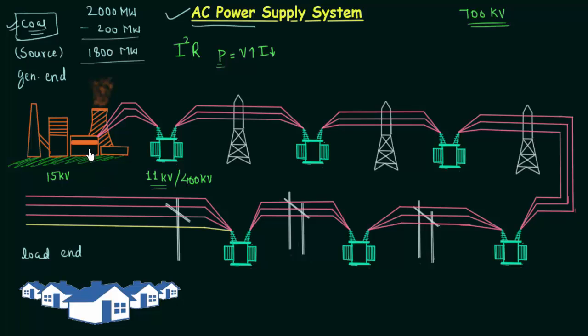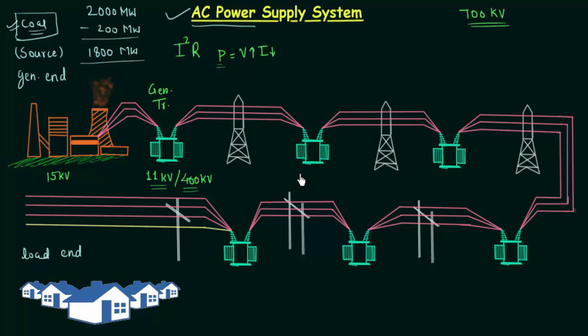Along with the generator, we require a transformer acting as a step-up transformer, which we call the generator transformer. It is the same as other power transformers, but its operation is different: the generator transformer always works as step-up, whereas general power transformers can work as step-up or step-down. So there is always a generator transformer associated with the generator to step up the voltage. Once the voltage is stepped up, we transmit it over a long distance, and at the load end we need to step it back down.